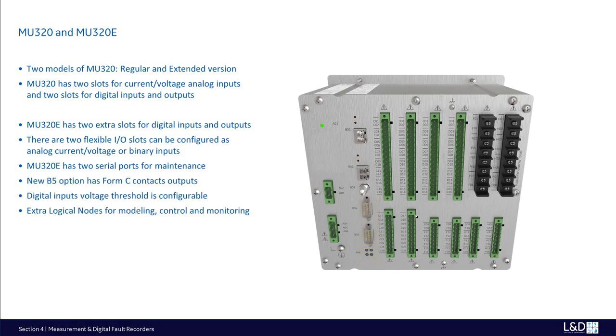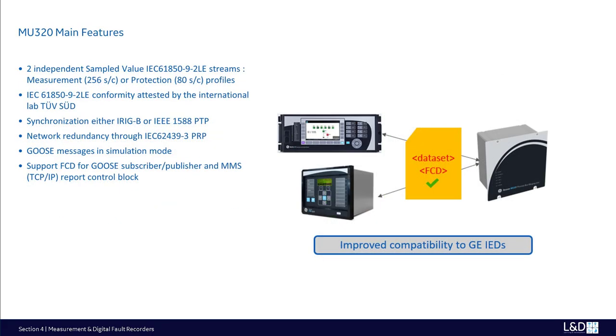A new B5 option has Form C contact outputs. The digital input's voltage threshold is configurable, and there are extra logic nodes for modeling like control of circuit breaker, XCBR, and switchgear, XSWI, and for self-monitoring, LCCH, LTMS, and LGOS, etc. MU320 has 2 independent sample values IEC 61850-9-2LE streams, measurement of 256 samples per cycle, or protection 80 samples per cycle profiles.